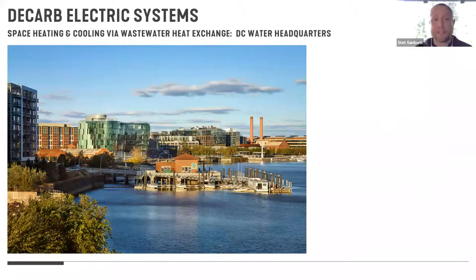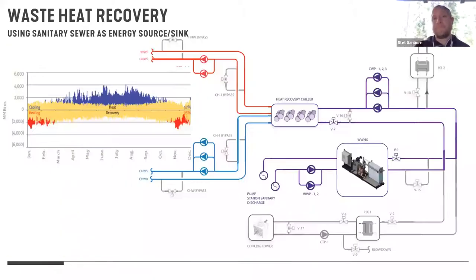So this particular project is a SmithGroup project. It is the DC Water headquarters in Washington, DC. It's a commercial office or administrative building, and it has the benefit of sitting over a large pumping station. So in this case, there's no sewage tank that we need to help balance the energy flows and storage of that source energy sink. It's actually on top of a pumping station, and so there's almost an unlimited source, if you will, of sink or source on the sewage side.